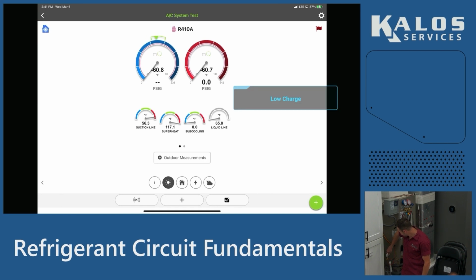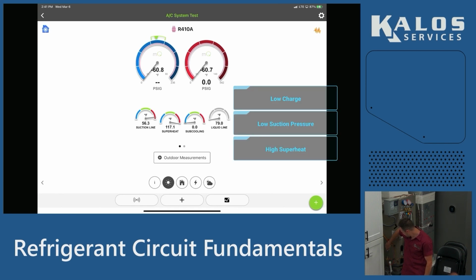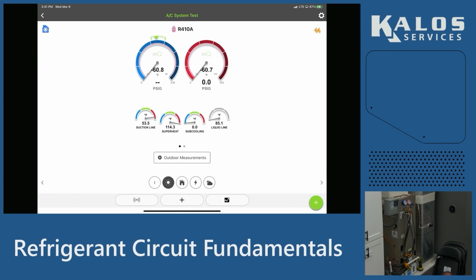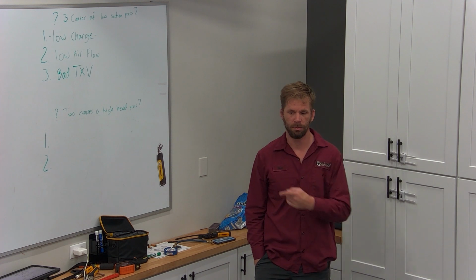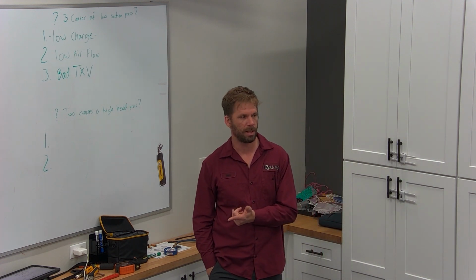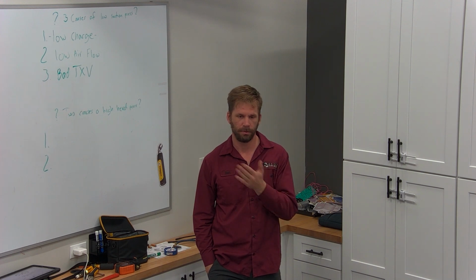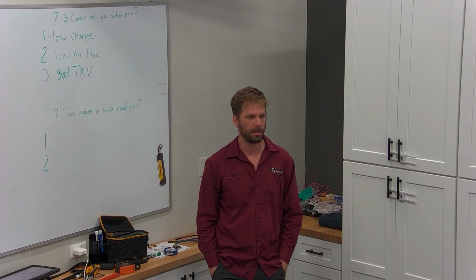If we have low charge, we already know our suction's low and our superheat's high. What is it going to be like on our head side? High pressure. I didn't say low pressure. We'll have a high pressure, okay? He says low. What do you mean by low though? Low's relative. You don't have to guess a number. Low compared to where it should be, maybe? It probably was the average number. Okay, an average. If we use his rule of thumb, it would be low compared to that, what was it, 12 to 15? Yeah, it'd be low, the saturation.